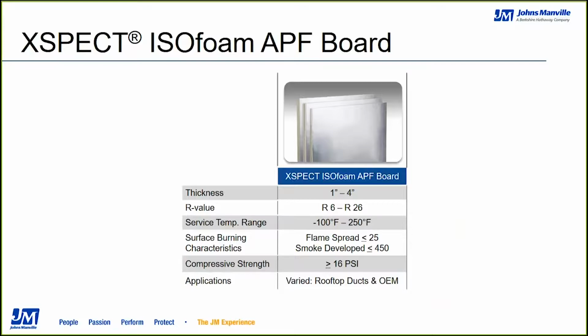And those of you that are quick with math can see that when you have additional thickness of polyiso boards, you do pick up some additional R value as well. So a 2-inch board of XSPECT will have an R value of 13, while the R value on 1 inch is only R6. The surface temperature range is -100 degrees Fahrenheit up to 250 degrees Fahrenheit. And the surface burning characteristics as defined by ASTM E84 are 25 flame spread and 450 smoke development.